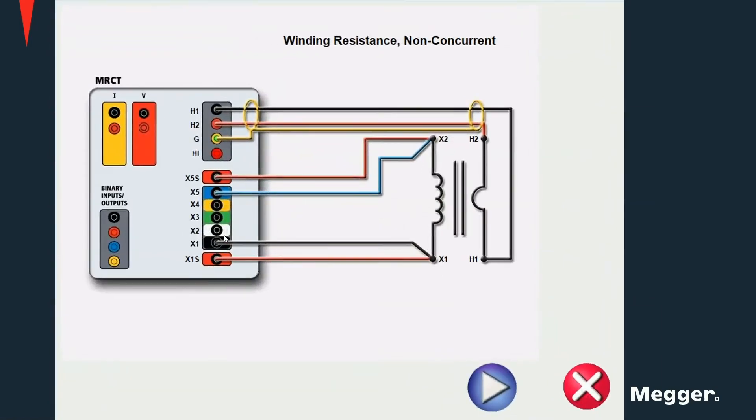For a two-tap current transformer, connect the X1S and X5S terminals to the X1 and X2 terminals on the current transformer as well as the primary side terminals. In this case, we are doing a winding resistance test in which a current is injected into the secondary of the current transformer. A voltage is measured and the resistance is calculated as the ratio of the voltage and current.